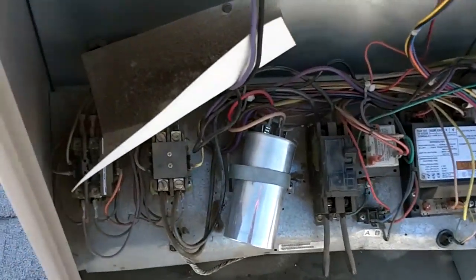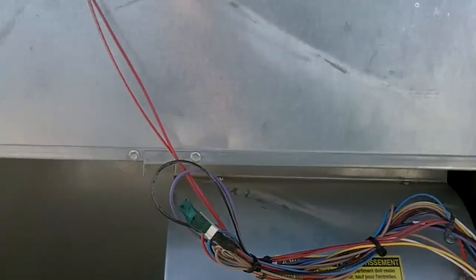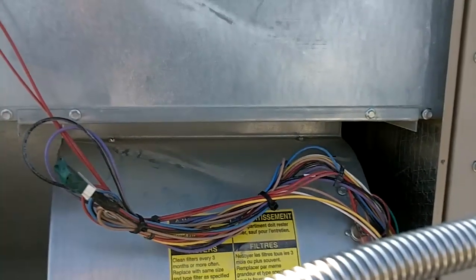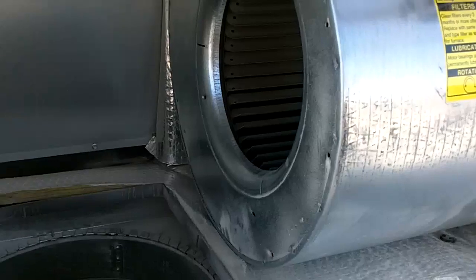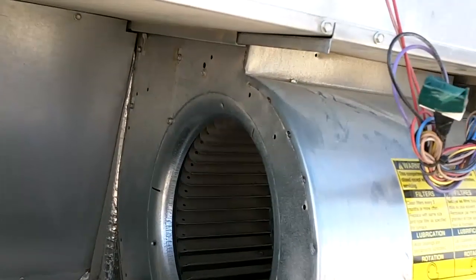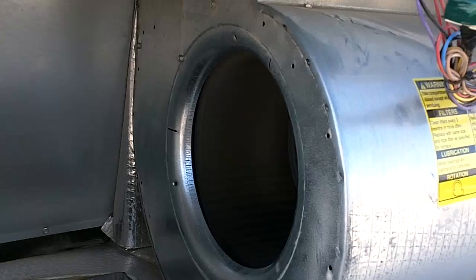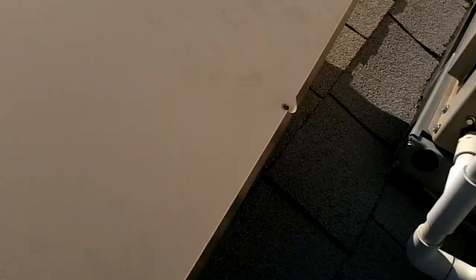I'll fix that run cap at least. I got that glow bar going. Pilot's lit. Just keep the fingers crossed — let's see. I hope the only sparks, the only fire, is in the firebox up there. There we go, there we go — back downtown. And that, my friends, is an ECM to X13 conversion.